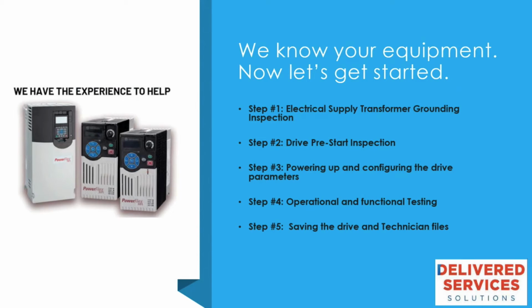Some of the steps we follow during a drive startup is verifying electrical supply transformer grounding, whether that's delta or Y on your supply transformer. A drive pre-start inspection where our technician will come out and verify the I/O and power wiring to the drive to notice any inconsistencies and make sure you're wired properly. Powering up and configuring the drive parameters for your application. They'll also do operational and functional testing, and they'll save the drive and technician files. So you can use those down the line for troubleshooting or any other reasons you might need them.